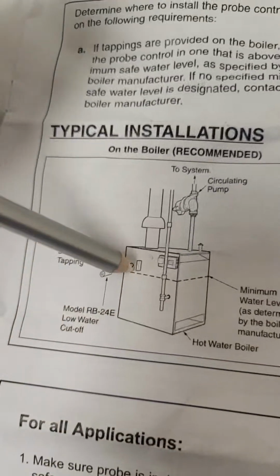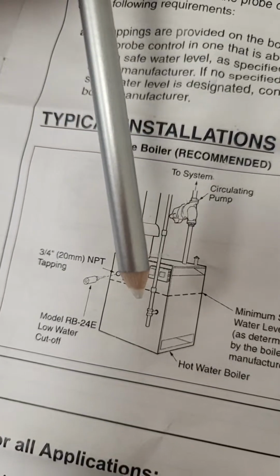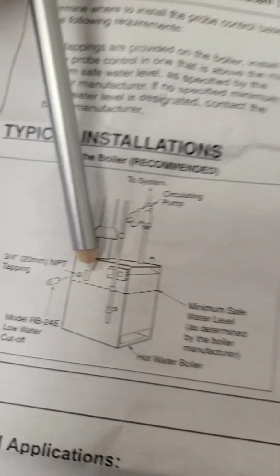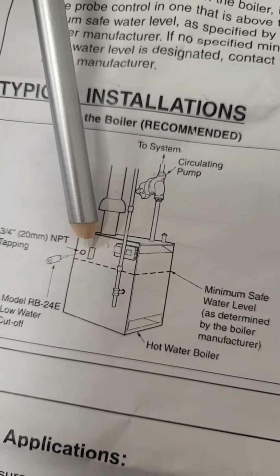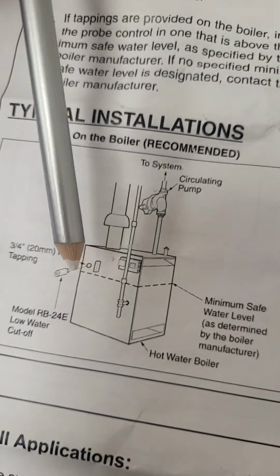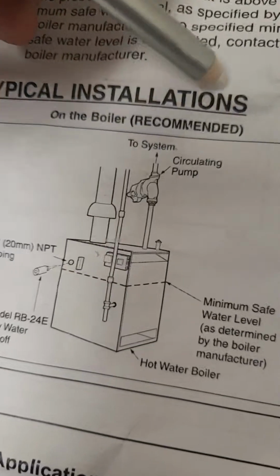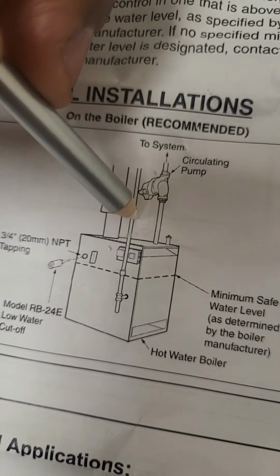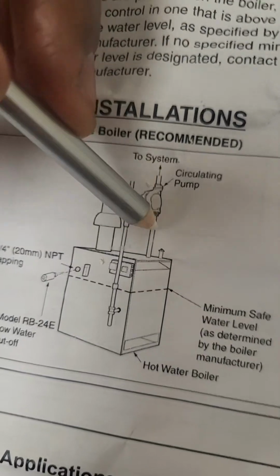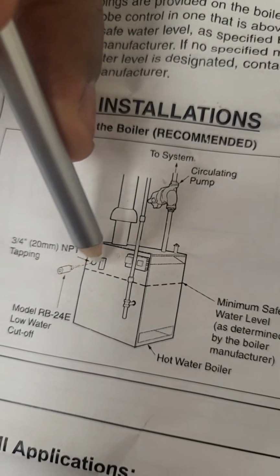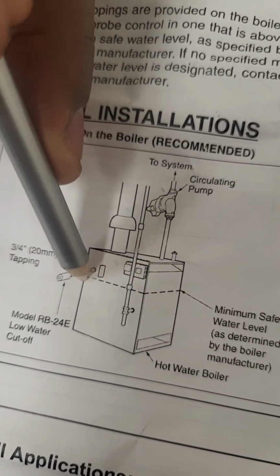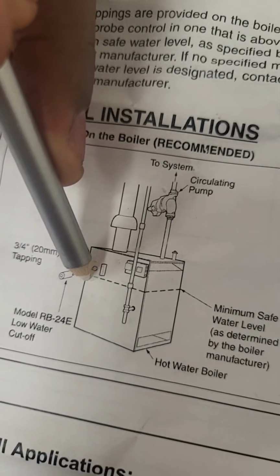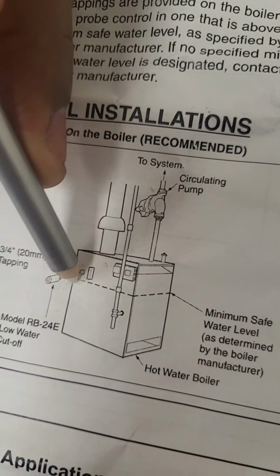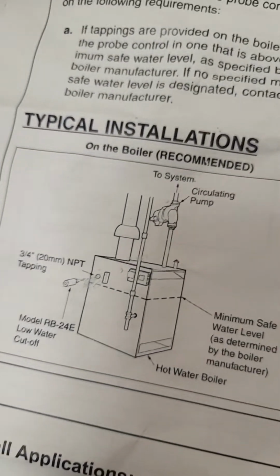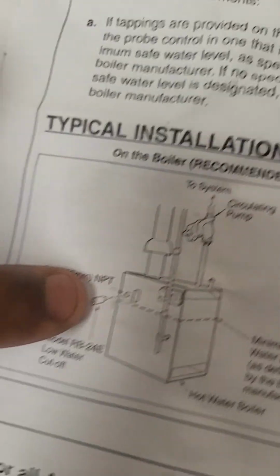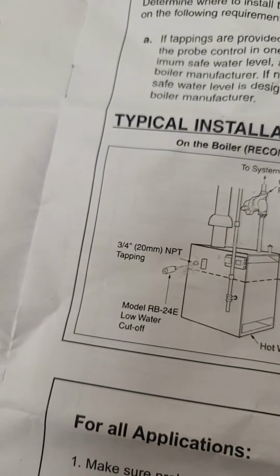Now what I've seen is there's one or two ways to do this, depending on the age of the boiler. If the boiler is 100 years old, I'm not recommending you open up the tapping on the side of the boiler. I'd rather cut into the supply or return line. It's easier to do, you have more space, and getting that 3/4 cap out the side of a boiler past 20 years old, I feel like if you open that tap up it might leak.